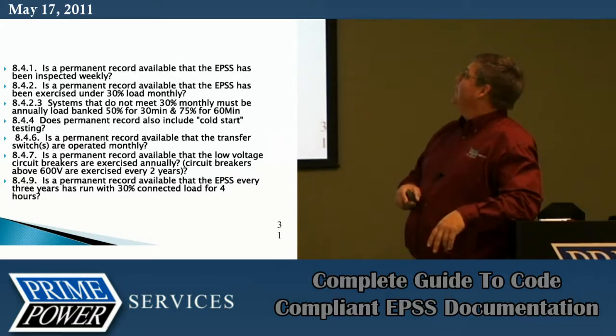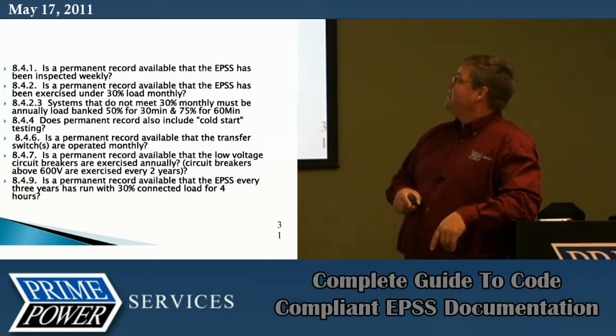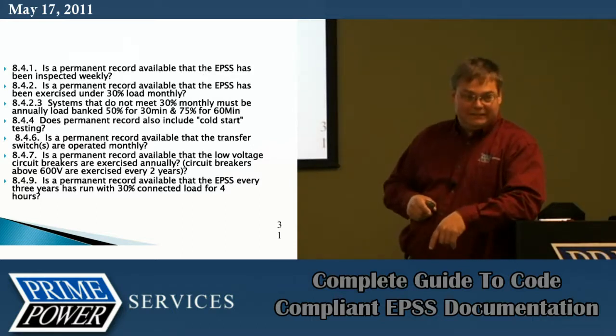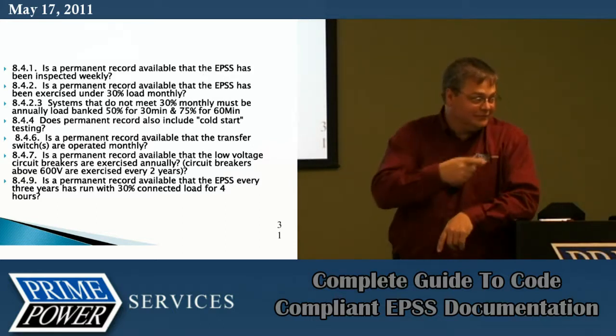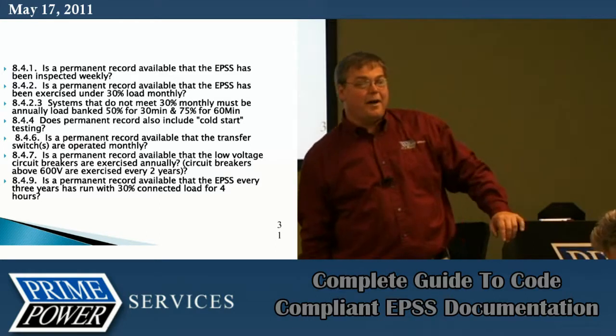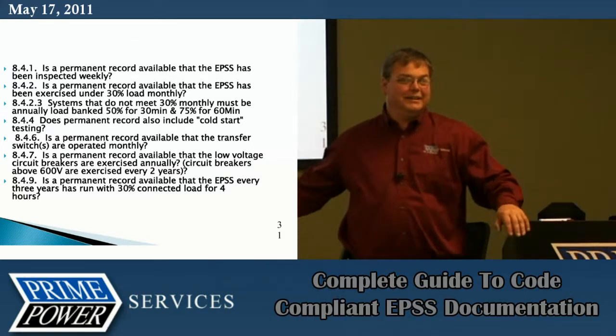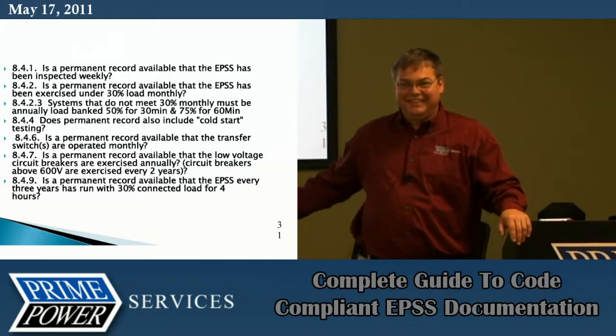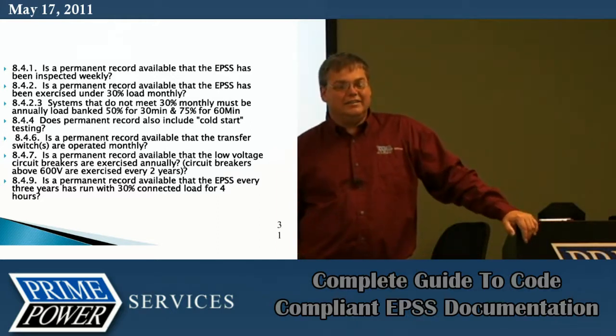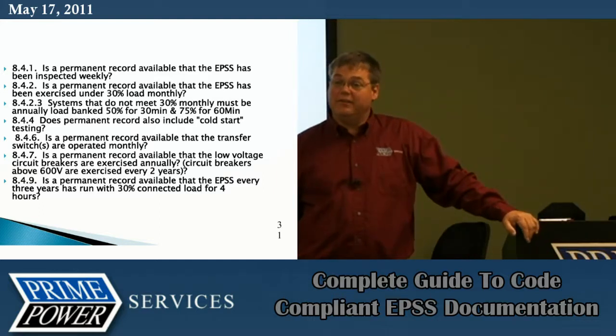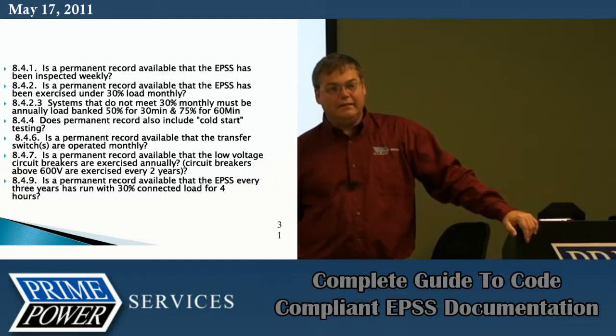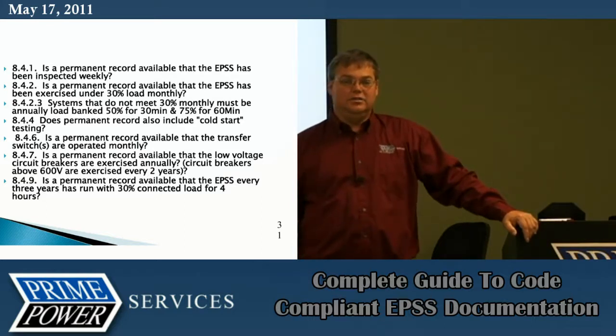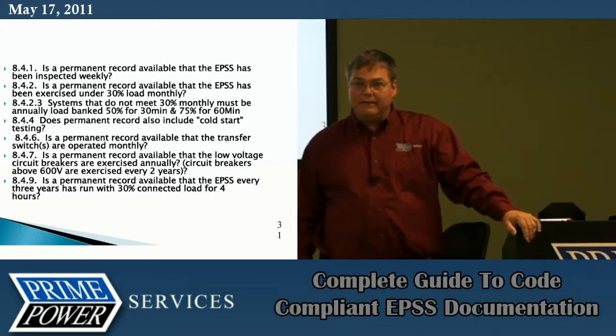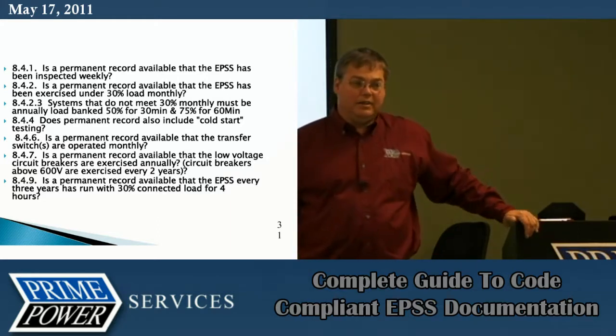Is a permanent record available that EPSS has been exercised under 30% load monthly? We read the code direct earlier. There's 3 options there. Do we need to cover that one again? There was quite a bit of confusion on it. The idea behind this standard is that you've got to run this generator. They want you to run it monthly. They want you to run it at 30%. If you cannot meet that 30%, then you have the other options to go by. But they're looking.